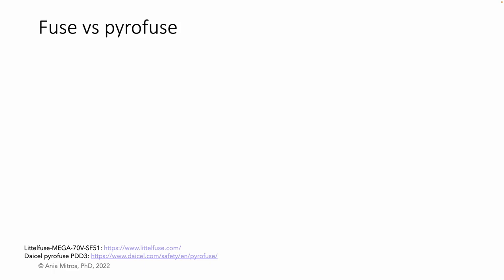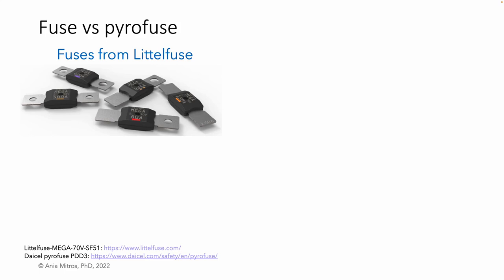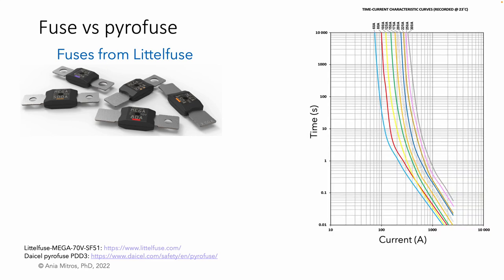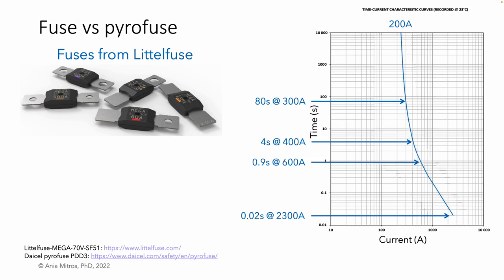Let's take a closer look at fuses versus pyrofuses. A fuse contains a metal strip or wire that opens when the resistance of the element generates enough heat. Every fuse datasheet contains curves showing the opening time as a function of the current. For any given fuse, the opening time gets shorter with increasing current. Let's look at the curve for the 200 amp fuse. Here, I've labeled some of the opening times.